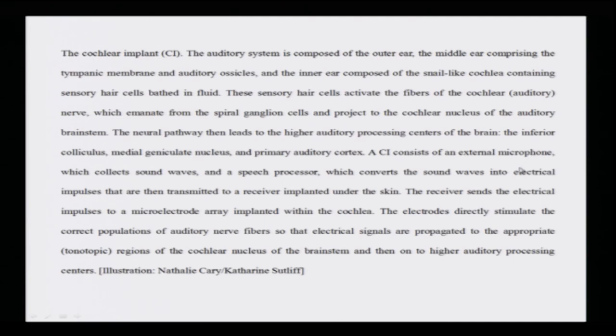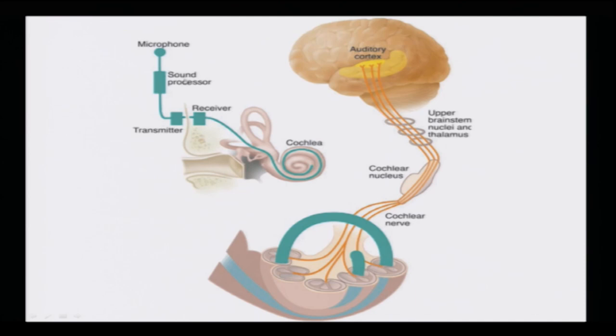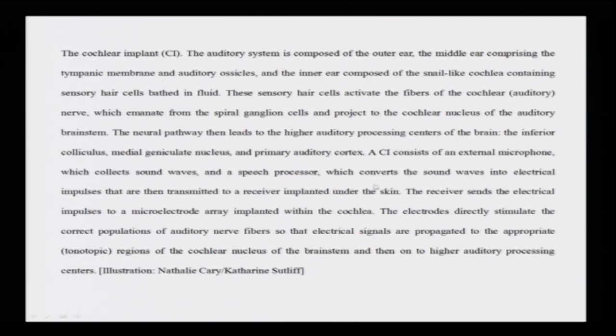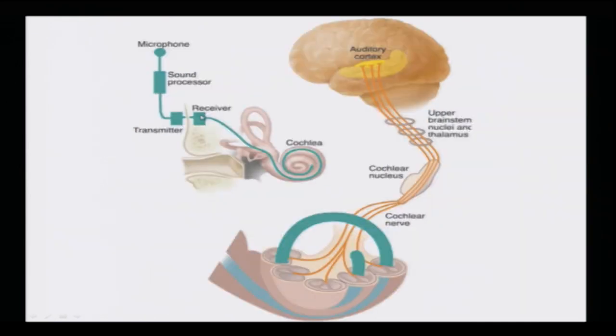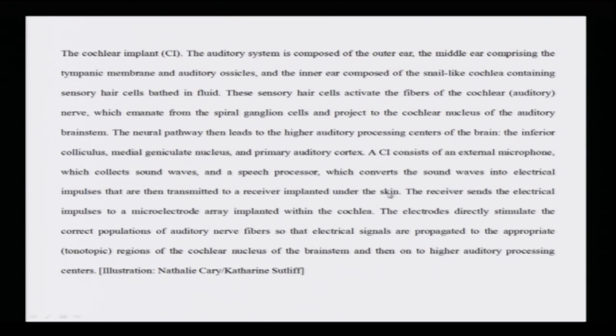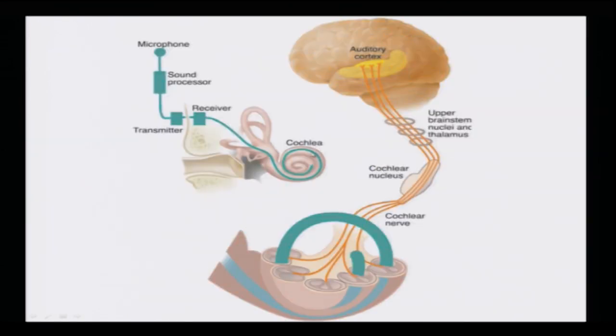The cochlear implant (CI) consists of an external microphone that collects sound waves, a speech processor that converts sound waves into electrical impulses, and a transmitter that sends these to a receiver implanted under the skin. The receiver sends the electrical impulse to a micro-electrode array (MEA) implanted within the cochlea. This is where MEAs find their application — understanding cell-electrode interfacing is a very important criterion for the success of these implants.